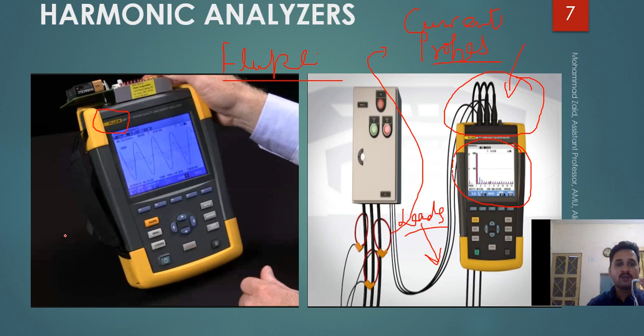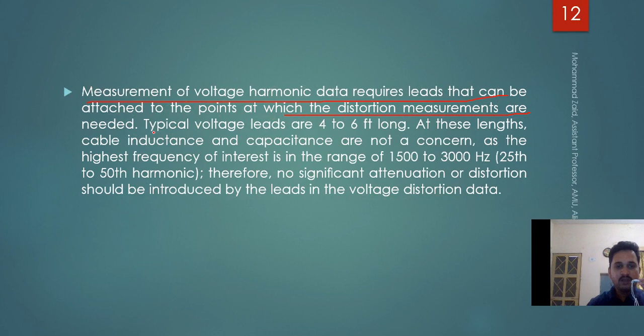So that is being told here. This is a current probe, this is also a current probe. Okay, so measurement of voltage harmonic data requires leads that can be attached to a point where the distortion measurements are needed. Typical voltage leads are 4 to 6 feet long. How much? 4 to 6 feet long. At this length, cable inductance and capacitance are not a concern.